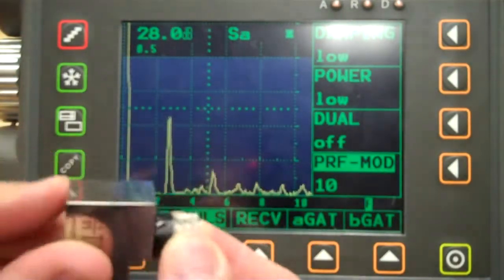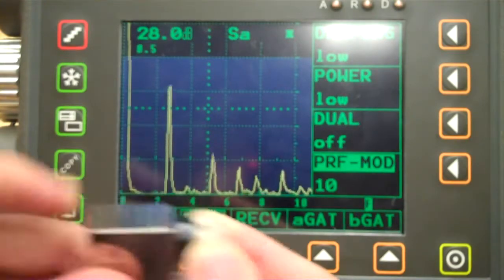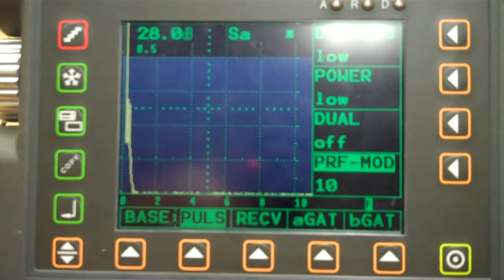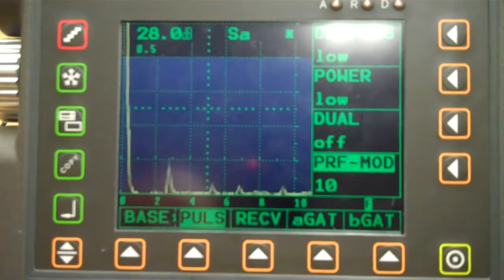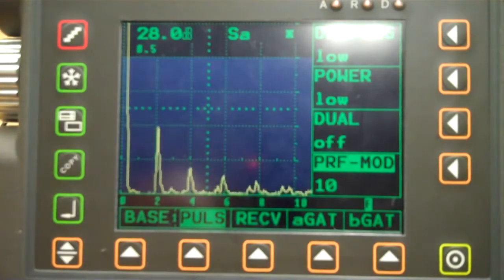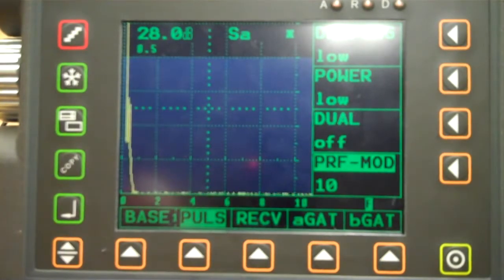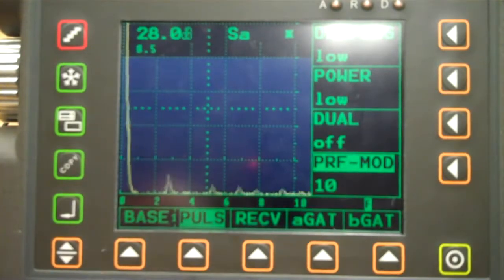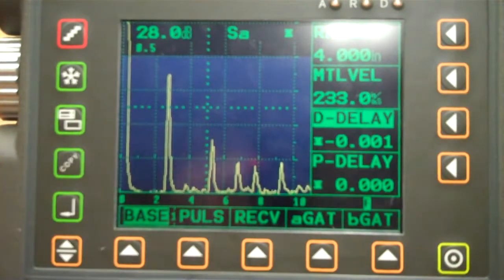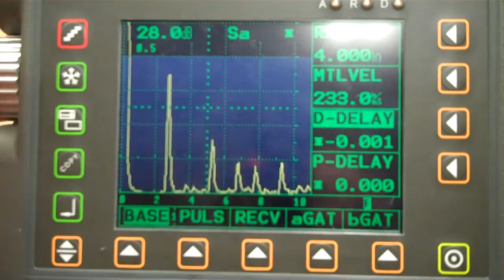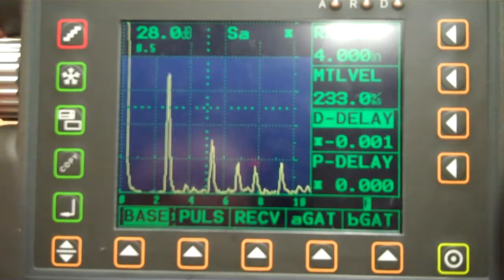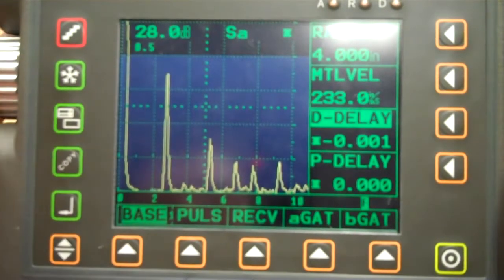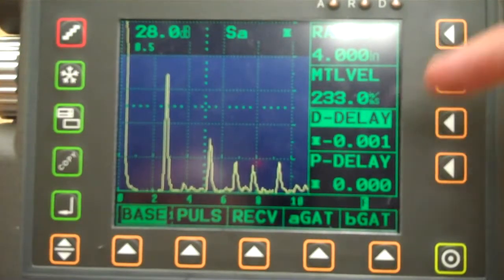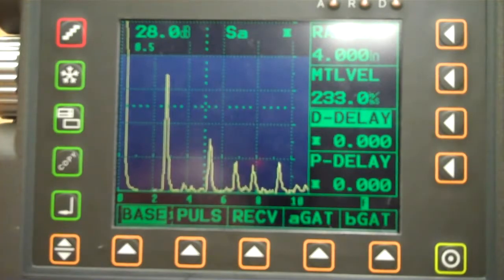So now we're on the 1 inch thickness. Look at it here and then I'll move it. 1 inch thickness, okay? There's our 1 inch thickness, 1/2 inch thickness, or sorry, 1 inch, 3/4 of an inch, 1/2 an inch, 1/4 of an inch. Since we're going to be calibrating to 4 inches of range, we're going to want to mess with the 1 inch and 1/2 inch steps. Okay? So now we need to see 4 inch range, steel, there's my delays, I want that at 0.